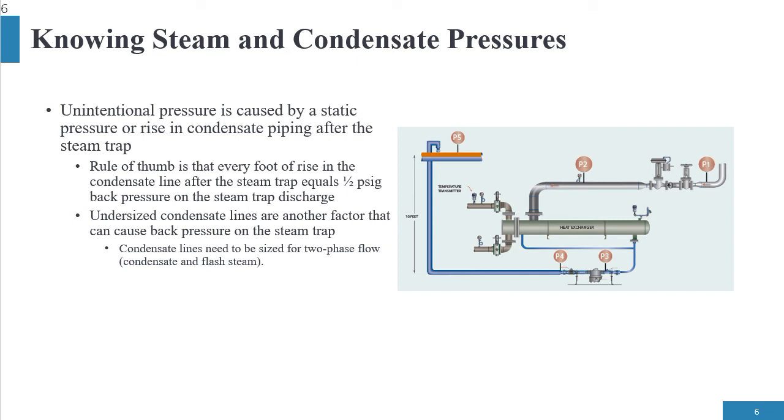The other thing is that we take a rise after the steam trap, there's going to be back pressure. The rule of thumb is a half a psi for every foot rise in pressure. So therefore, there is going to be back pressure onto the steam trap or down here at P4.